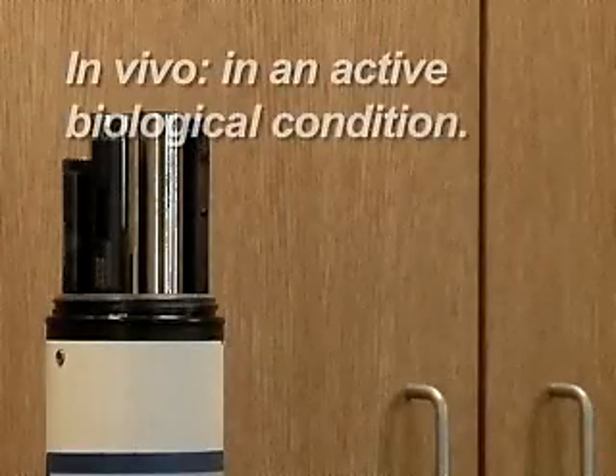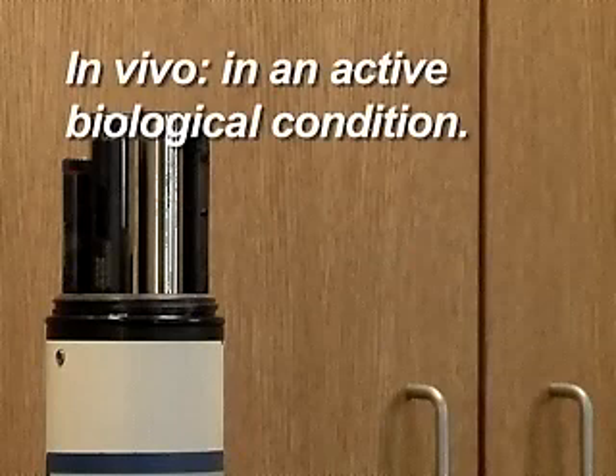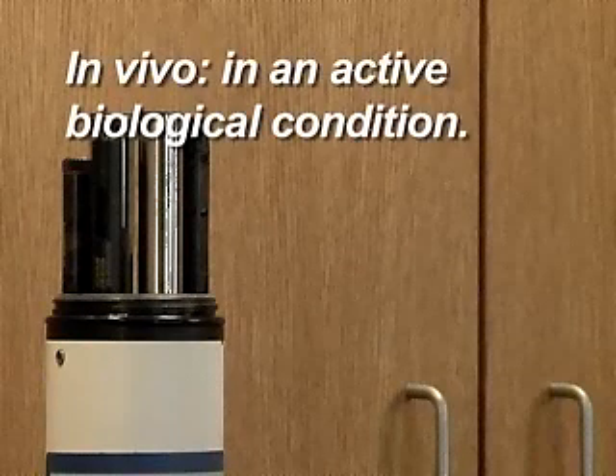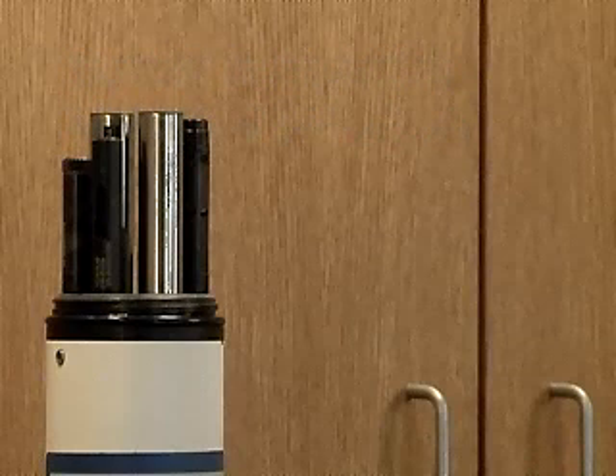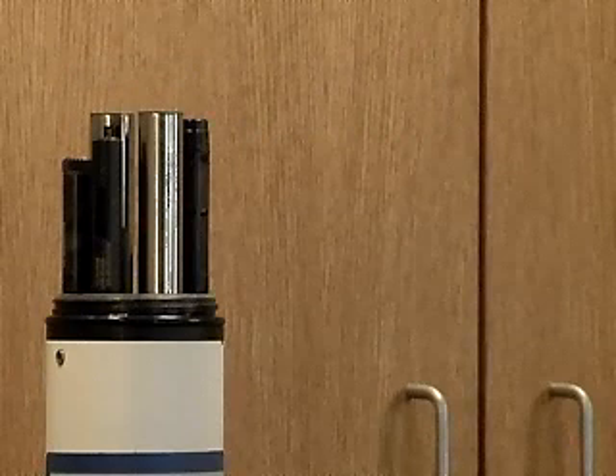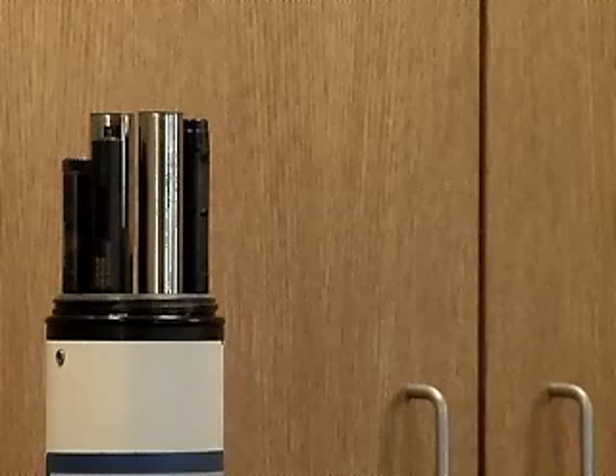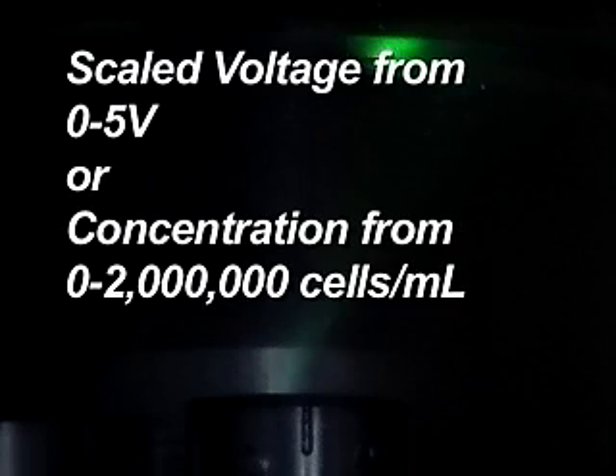Monitoring in vivo, that is, an active biological condition, is subject to a great deal of variability. The fluorescent properties of a cyanobacterial population in a body of water can change with the health of the organisms, temperature, and exposure to light, even while the concentration remains the same. This makes in vivo data useful for trending or for correlating relative measurements to more quantitative values. The readings can be reported as a scaled voltage from 0 to 5 volts or as a concentration from 0 to 2 million cells per milliliter.